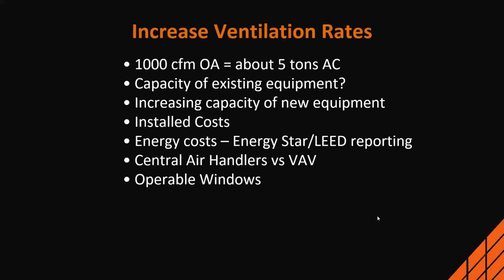Will the ventilation rates be noticeable to the average occupant, like the increase in rates that you're showing? If you can push, what can happen during the summer is you can start to lose a little bit of control of the humidity because we're going to be focused mainly on the temperature. And then also if you're running the VAV boxes, if you have a VAV system and you start running the minimums higher, you might overcool the space. So you are going to have the possibility of making some trade-offs for comfort. But there's some other ways to address that down the road.